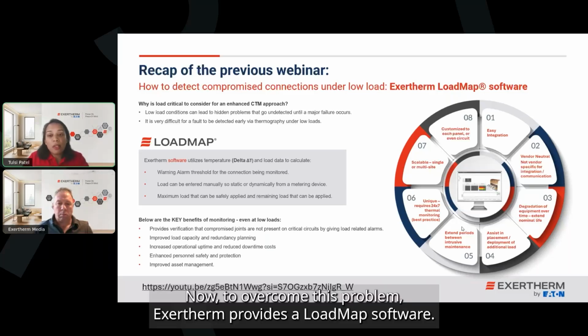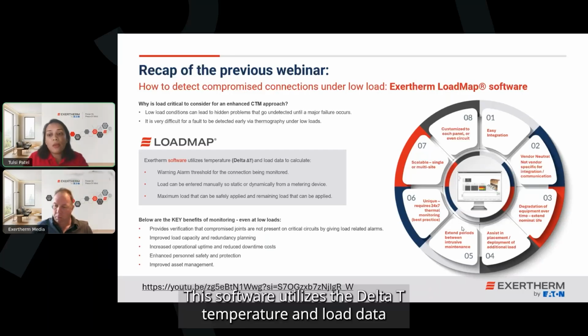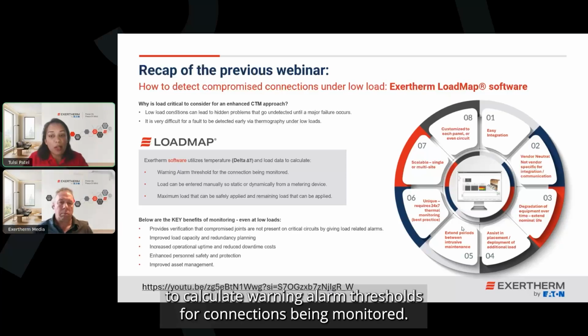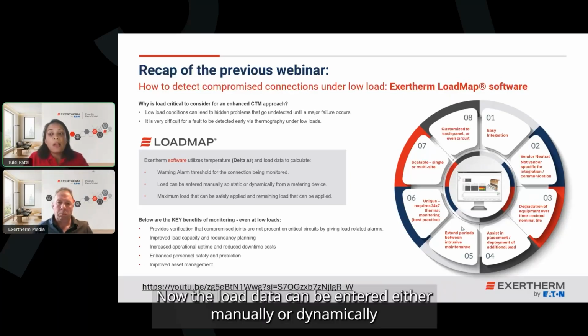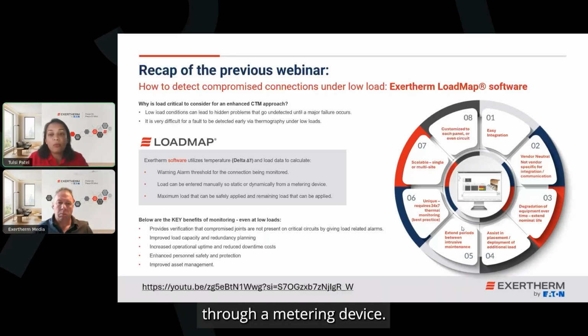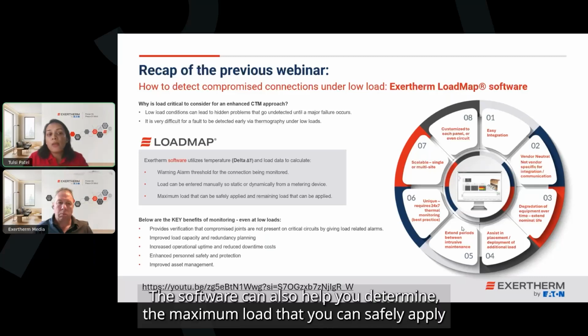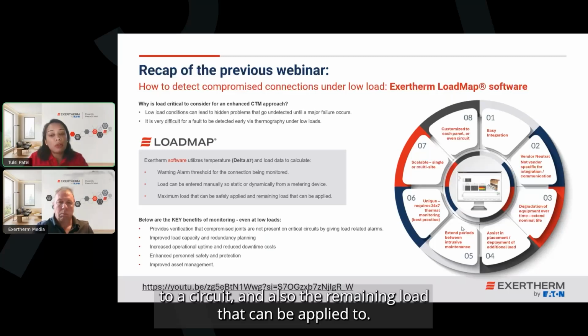Now, to overcome this problem, Exertherm provides a LoadMap software. This software utilizes the delta T temperature and load data to calculate warning and alarm thresholds for connections being monitored. Now, the load data can be entered either manually or dynamically through a metering device. The software can also help you determine the maximum load that you can safely apply to a circuit and also the remaining load that can be applied to it.